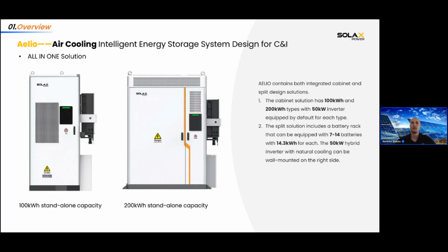So our first product is from SolaX, the new AELIO. This specific ESS is DC coupled. So you have a hybrid 50 kilowatt inverter on the side, as you can see on the picture. There are two versions of it, a 100 kilowatt hour battery and a 200 kilowatt hour battery, with a 50 or a 60 kilowatt hybrid inverter on the side. So you can achieve 2 C charging and discharging, and it's air cooled for now. It's already available to order from August, and there will be an updated version of the 200 kilowatt hour. It's going to be available in Q4, which will be water cooled.